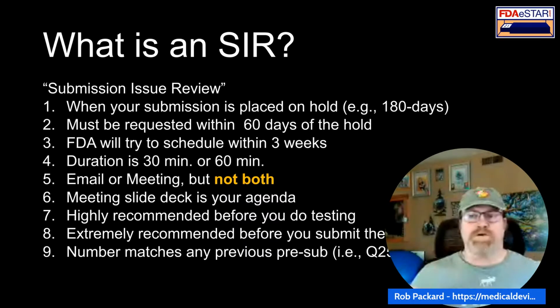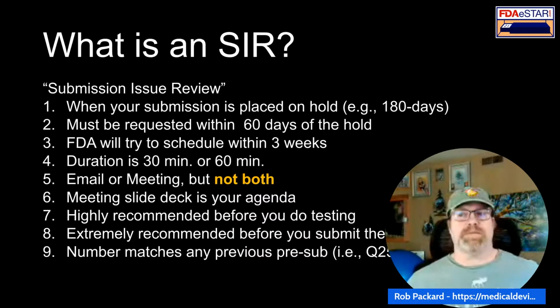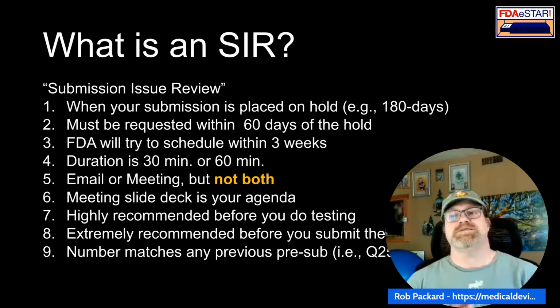Other things that are important to understand. The submission issue review meetings are what you submit as soon as you get a hold letter. So the FDA sends you a request for additional information. We call that an AI hold letter or an AI letter. That letter, you have 180 days to respond to it with your supplement. You must request your meeting within 60 days.